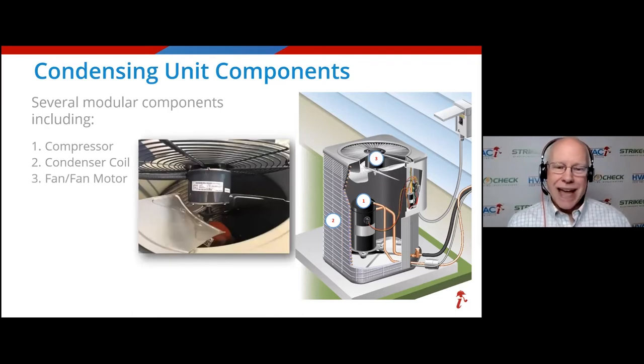Now we're going to talk about the fan and the fan motor, which is number three on this diagram. When it's running, one, it's probably making some noise. Two, if you put your hand above it, you have warm to even hot air being blown out of this unit. Before I knew how these systems worked, I just thought that fan is cooling down the unit, because whatever it's doing in there generating cold air, that motor's getting hot doing it. That's not what's happening, folks.